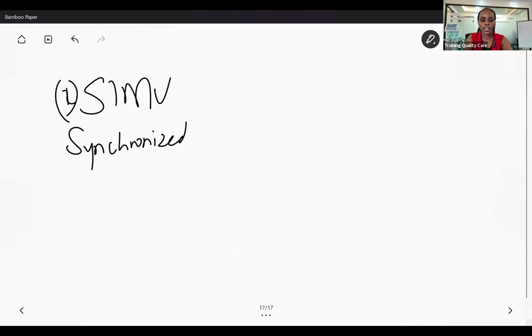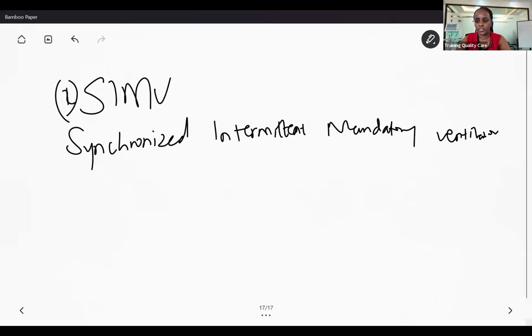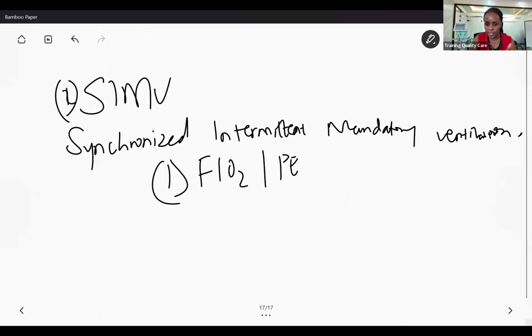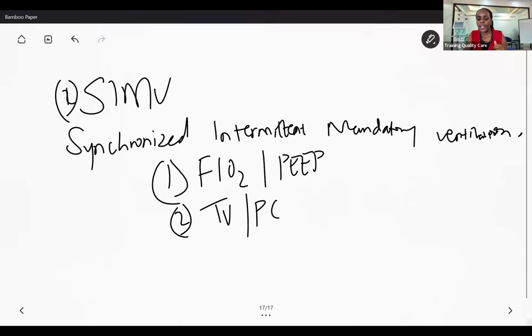The other common mechanical ventilator mode is SIMV. This is quite common. The full name is synchronized intermittent mandatory ventilation. For SIMV, this is a mode that gives mandatory breaths to the patient, and at the same time allows the patient to have spontaneous breaths. So what you are going to set first is the universal settings. We have the FiO2 and the PEEP, which are mandatory to set for all patients on a mechanical ventilator. The other thing that we are going to set is the major settings, where we are either going to cycle tidal volume or pressure control.